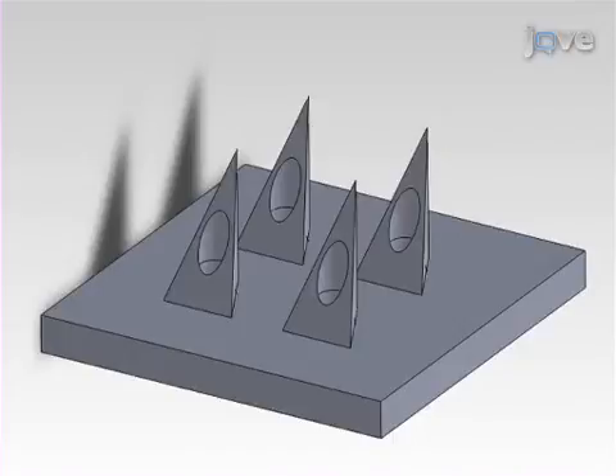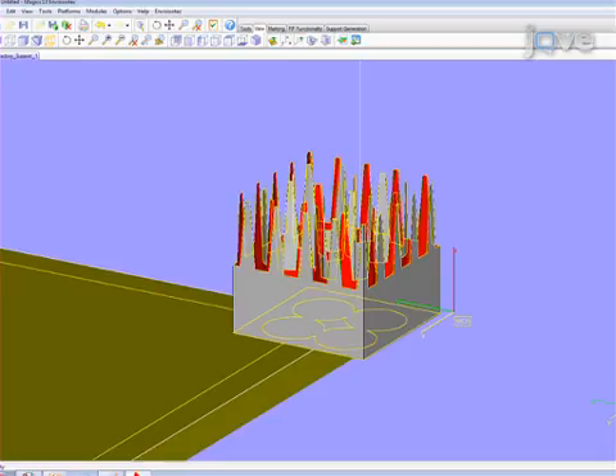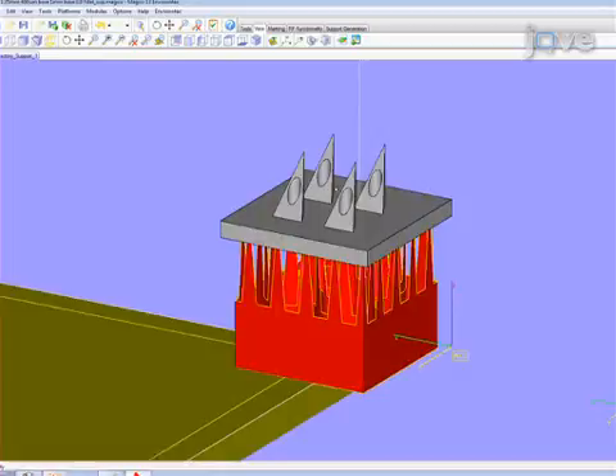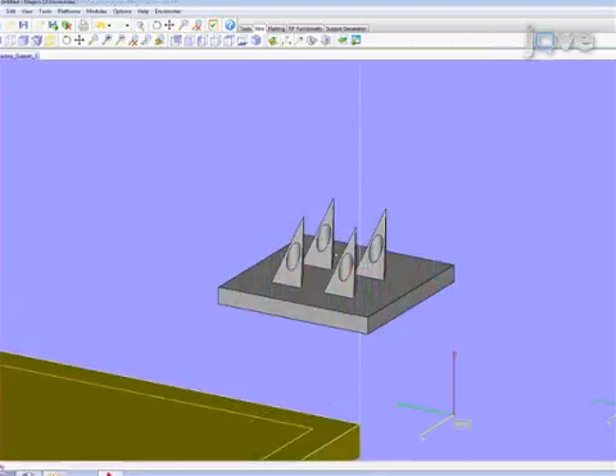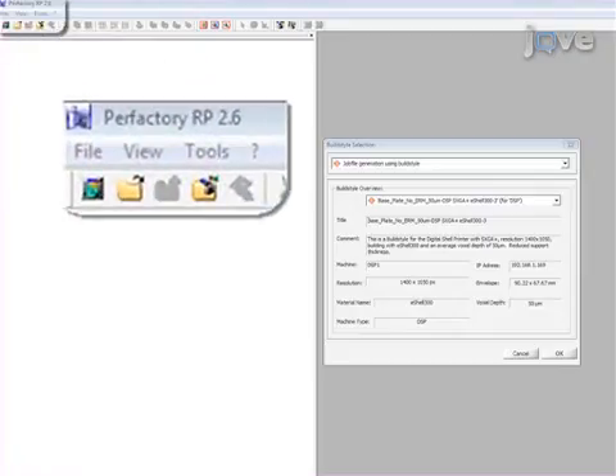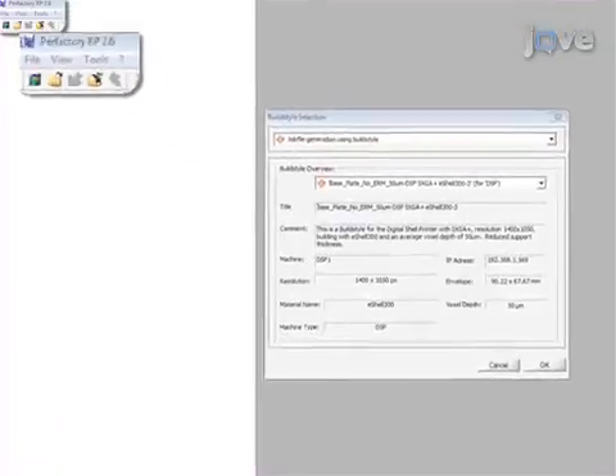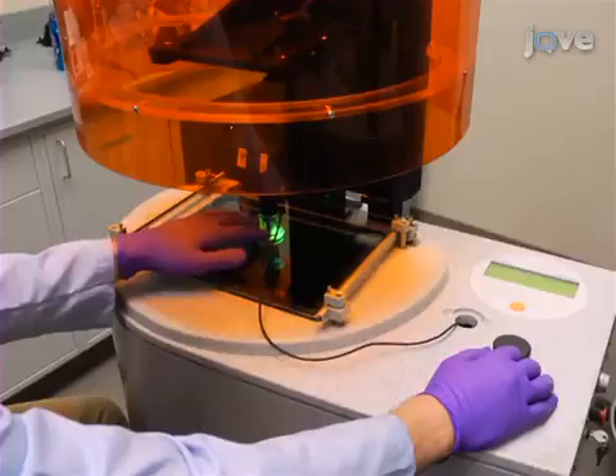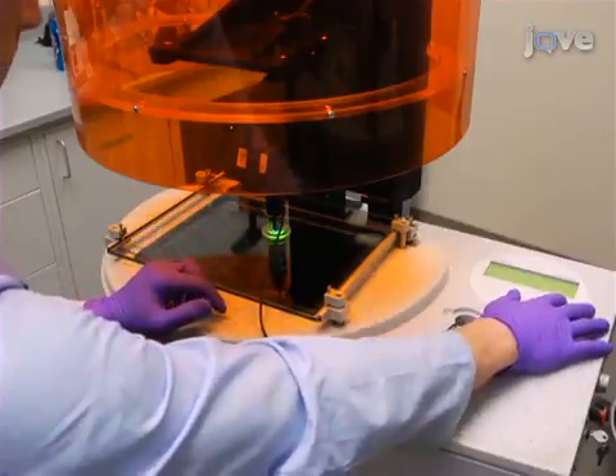Begin in the three-dimensional modeling software SolidWorks and design a pyramidal-shaped hollow microneedle array. Then, using the Magics RP13 software, design a support structure that provides a base on which the microneedles are built. Next, control the fabrication process using the Perfactory RP software. Upload both the linked support and the microneedle array files. Then select the number of microneedle arrays to be fabricated and determine the placement of devices on the fabrication plate. In the Perfactory Rapid Prototyping Manufacturing System, select Ultraviolet mode at 100 milliwatts and perform the calibration procedure. Verify the deviation in the energy is within plus or minus 2 milliwatts.